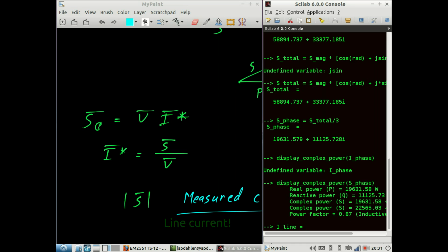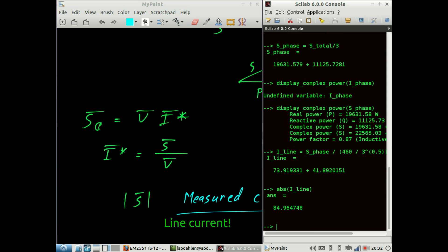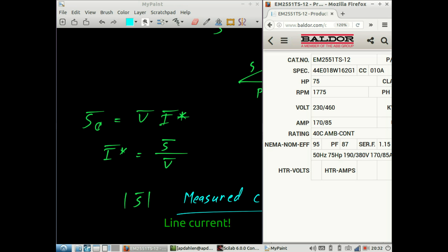Now we can calculate the line current, which equals S_phase divided by the source voltage — in this case 460 divided by the square root of 3. The absolute value of the line current is 85 amps, which is exactly what we had on the original datasheet for the motor. Please look below in the video description for a link to the Scilab functions used. If you have any particular electromechanical problems you'd like to see solved, please leave a comment.